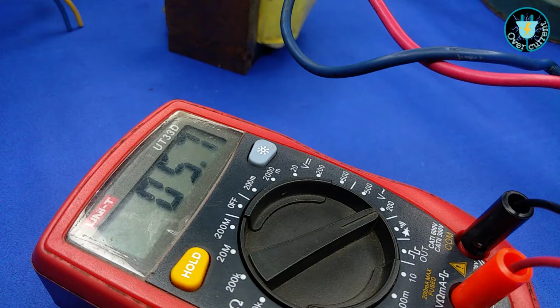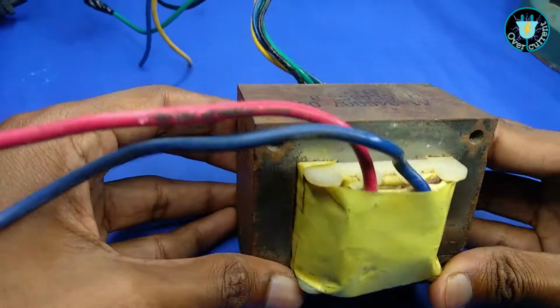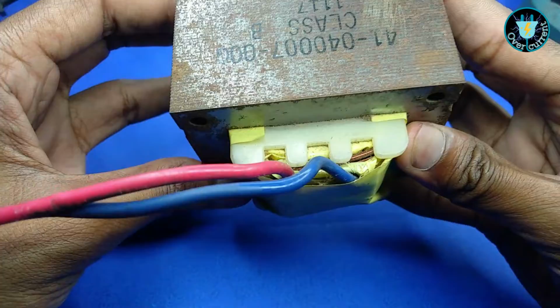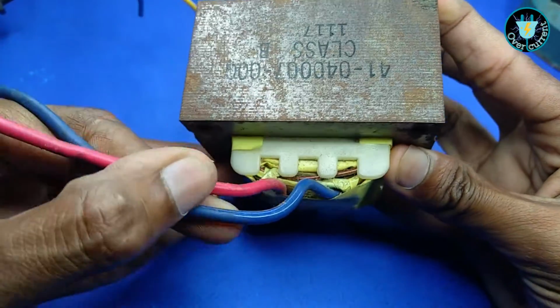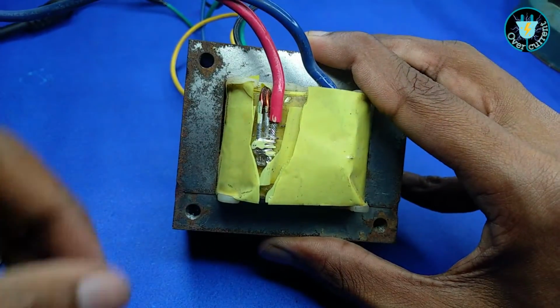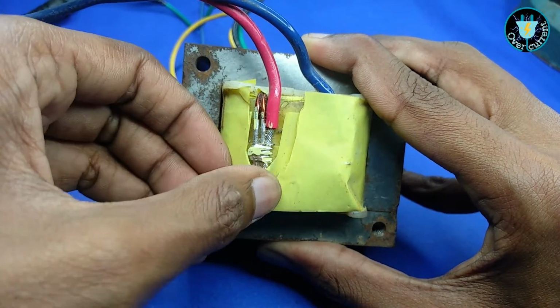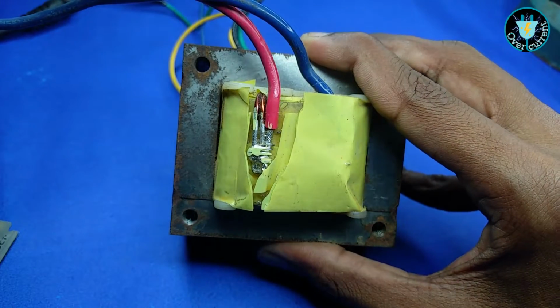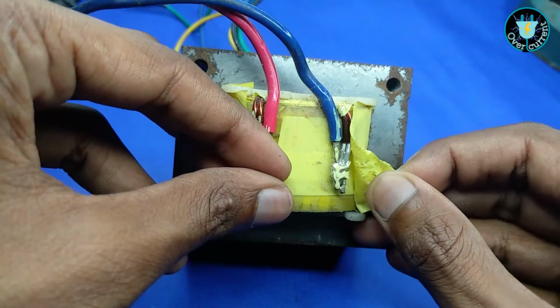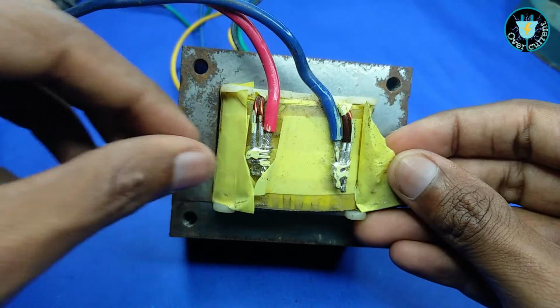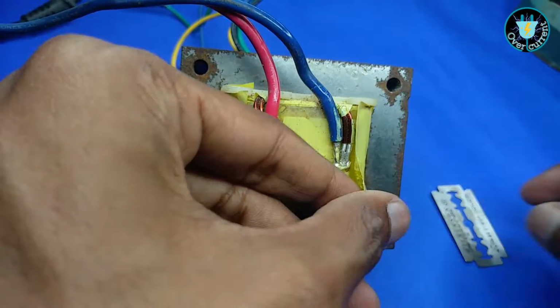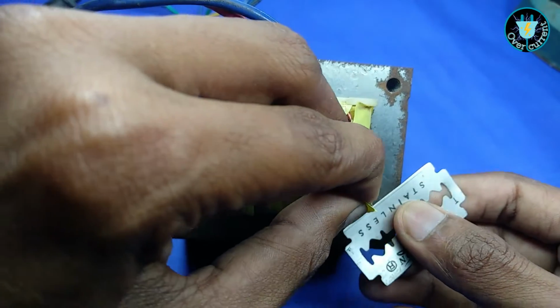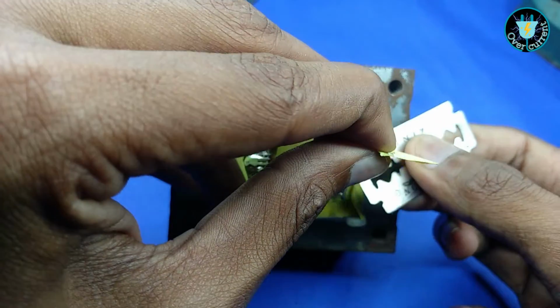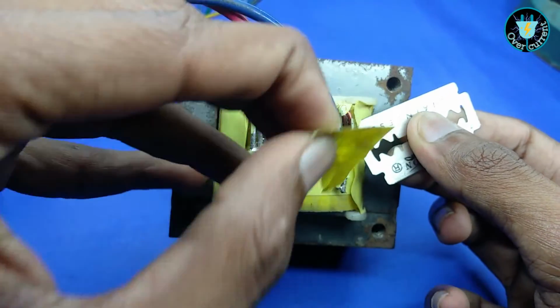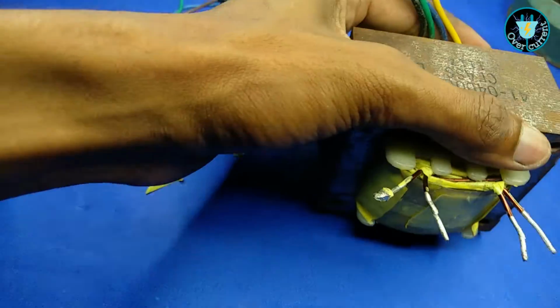So we need to do some modification in the secondary coil. When I checked the secondary side, I found something different. I cut the isolation tape and you can see there are 2 coils in the secondary connected in parallel. I need to separate the 2 coils and connect them in series, so I will get double the voltage in the output.